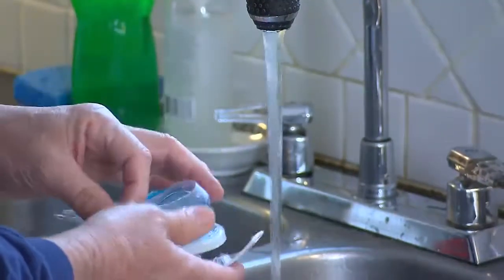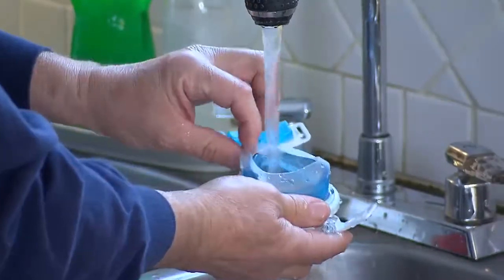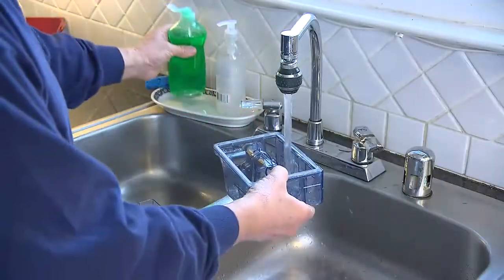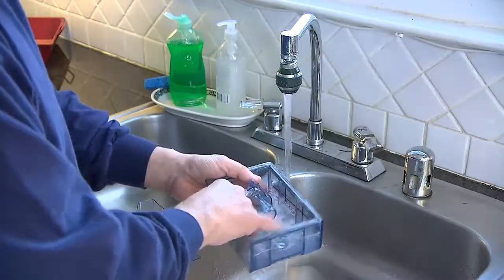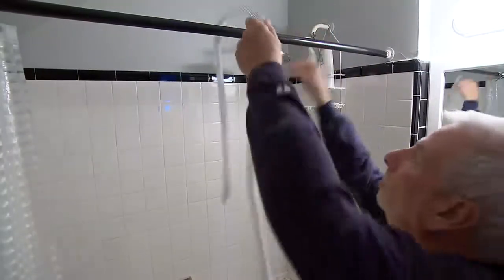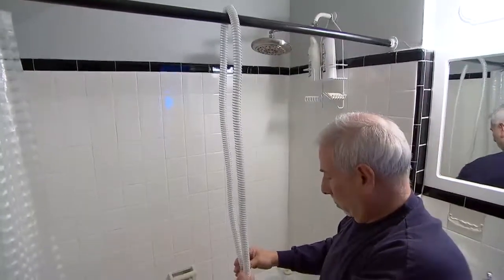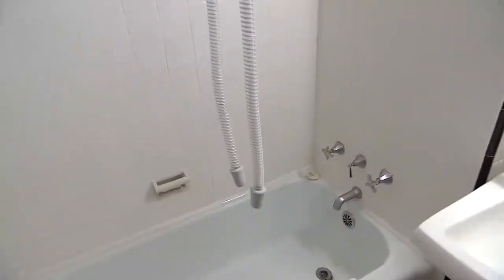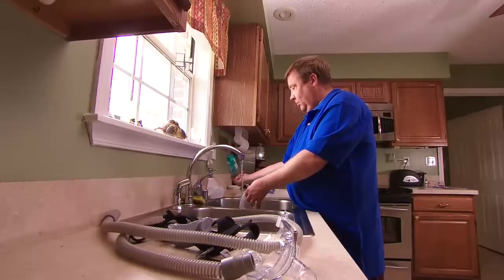Never secure the straps of the face mask too tightly on your face, and never use tape to seal the mask to your face. And of course, keep your mask clean. It'll fit much better if it is. Be sure to clean the humidification chamber too, since bacteria could grow inside of it. And hang your hose up between uses so all the condensed water vapor drains out and the hose can properly dry. Using detergents that contain conditioners or moisturizers to clean your face mask may cause residue buildup, so follow your manufacturer's recommendations in the labeling or package insert about the daily care and storage of your device.